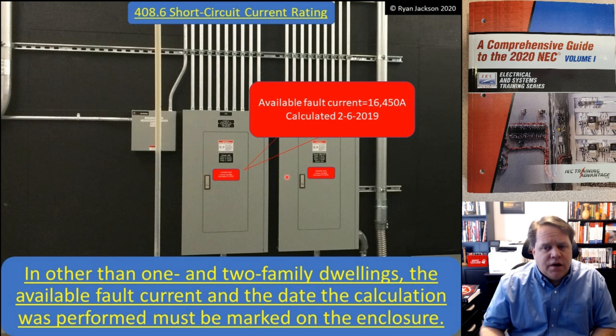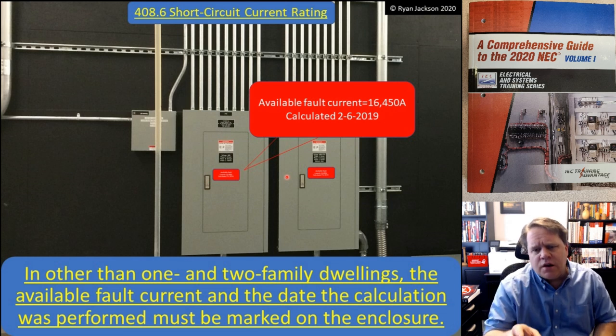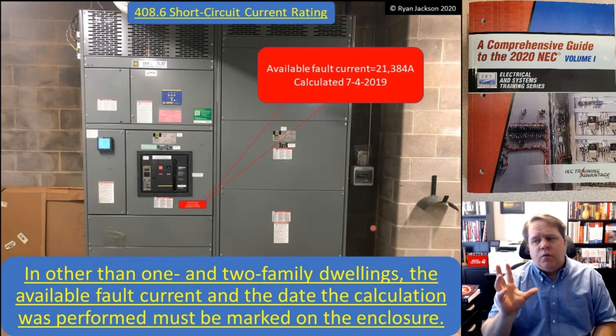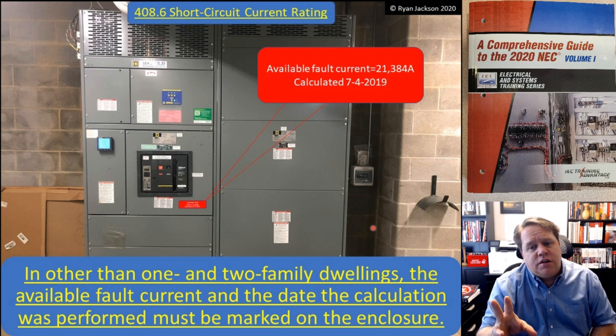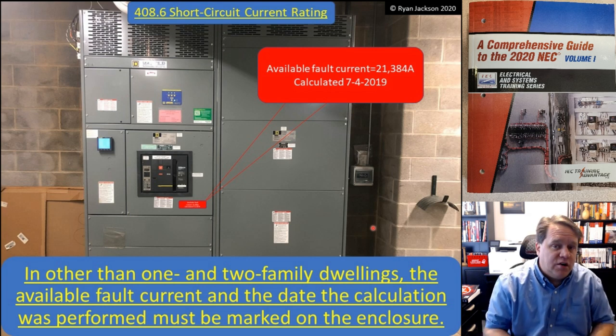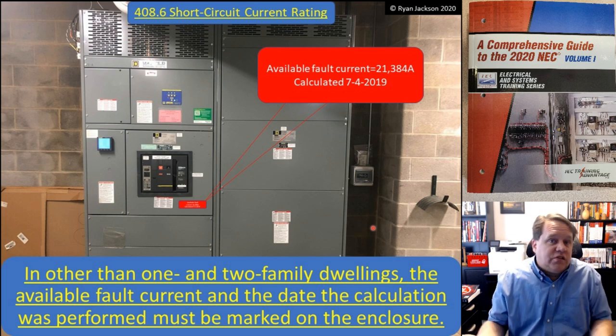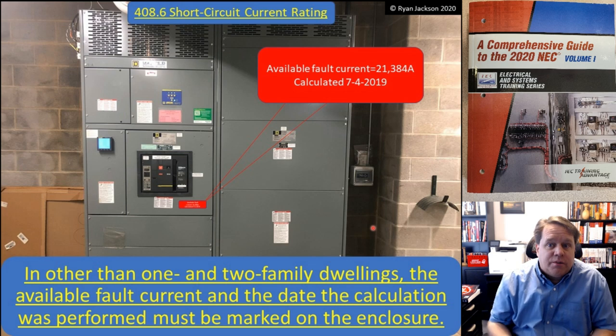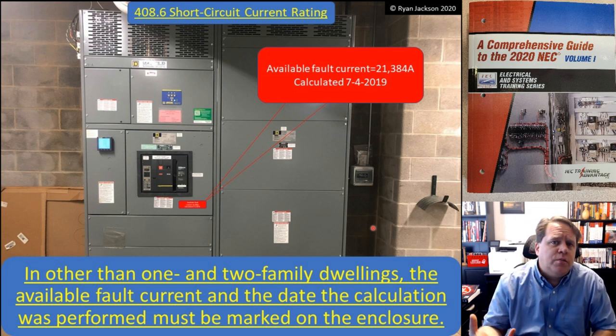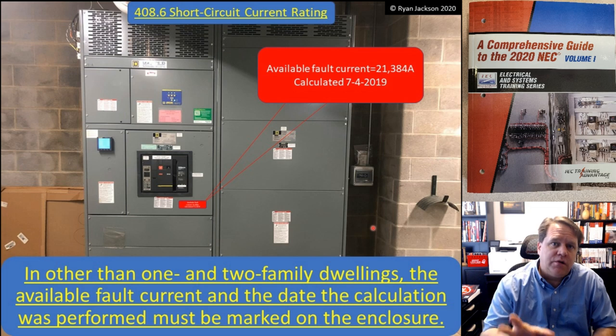I have to know the available fault current at every panel because I need to know what the short-circuit current rating of the panel needs to be. If I didn't know the available fault current was 16,450 amps, I might have mistakenly installed a panel rated only 10,000 amps. Something interesting: a lot of times when we look at a small panel we automatically assume the fault current will be rather low, and when we look at large switchgear we assume it'll be high. That's really not the case - it depends on many variables. At one application we marked 21,000 amps; it could just as easily have been 65,000 or 6,000 amps. Don't assume anything about available fault current without doing the calculation.